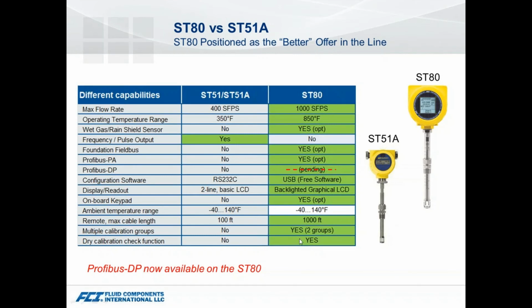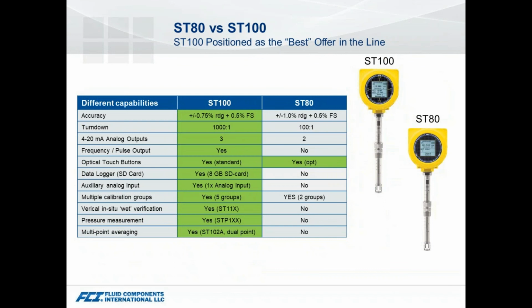And there's the dry check run, the self-validation, and I can actually put 2 different calibration groups in here. If I've got a process that has some seasonal changes, I can put in a gas mixture for each one of those seasons that I can switch through. Sometimes you'll see people using natural gas, and in the off season they might have to back it in with propane. You have the ability to put both calibrations in and use the calibration that's most accurate for your process conditions. Then stepping up from the 80 to the 100, there are some big changes here. This is our more accurate meter. We're looking at 0.75% of reading.